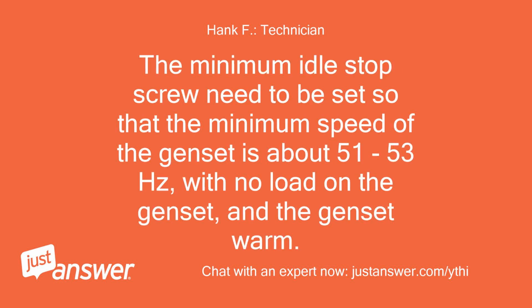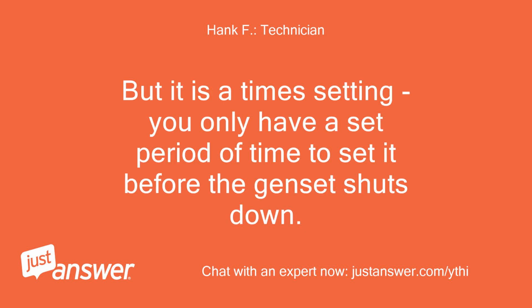The minimum idle stop screw needs to be set so that the minimum speed of the genset is about 51 to 53 Hz, with no load on the genset and the genset warm. But it is a timed setting, you only have a set period of time to set it before the genset shuts down.